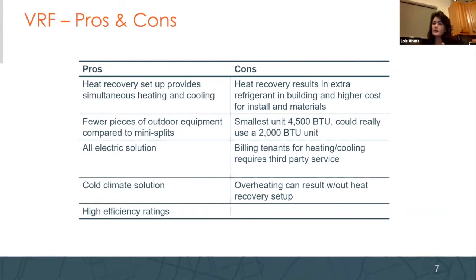Now, if we go to the con side, when you go to that heat recovery mode where somebody can do heating and somebody can do cooling at the same time, you actually have an extra refrigerant loop in the building, which means you have more refrigerant in the building. You actually have higher costs for materials and installation. The smallest units we can still get are somewhere around 4,500 BTUs. On the heating side, that's still too big. We could use something that's somewhere between 1,000 and 2,000 BTUs on heating, but then again, for cooling, we need probably at least double or triple that.